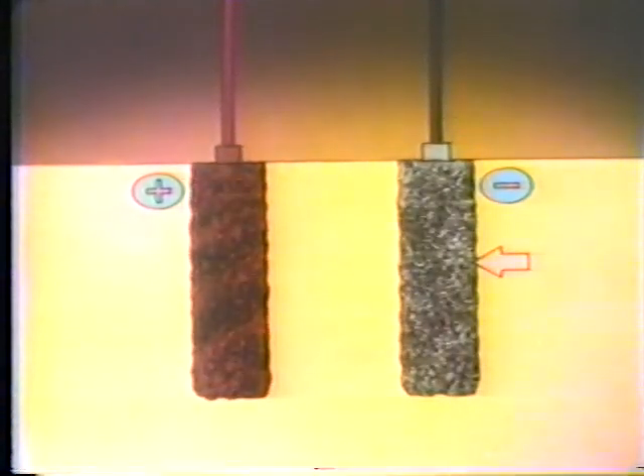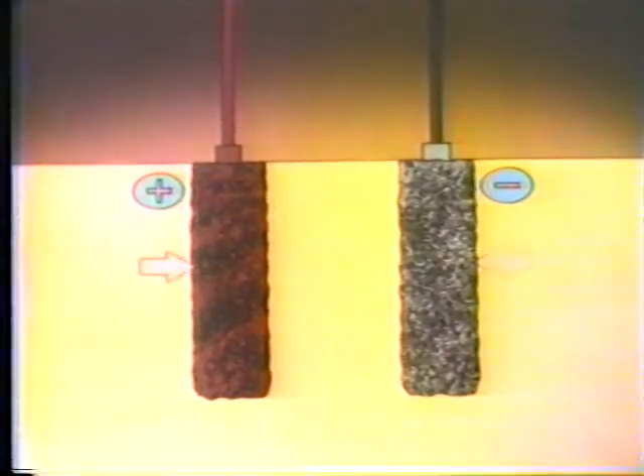When the plates are originally constructed, they're both composed of lead oxide, a dull grayish material. In this form, neither plate is electrically active. But when the cell is connected to a source of direct current — with the positive on one plate and the negative on the other — current begins to flow through the electrolyte. The action of the electrical current gradually turns the negative plate into pure spongy lead, and the positive plate turns to lead peroxide.